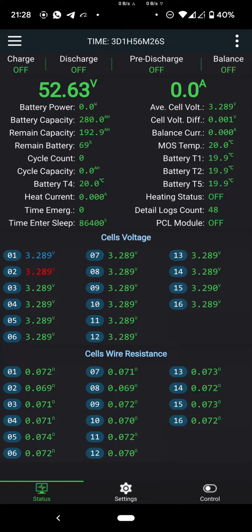On the other side, we have average cell temperature, cell voltage. Below we have delta voltage, or the difference between the highest and lowest cells. Then we have the balance current if the BMS is balancing. We have the heating status if the BMS decides it is necessary and if you enable it from the control tab. Below we have the voltages for all 16 cells. This BMS is also capable of working with 8 cells for 24 volt systems. And below that we have the cell wires, the cell's wire resistance.